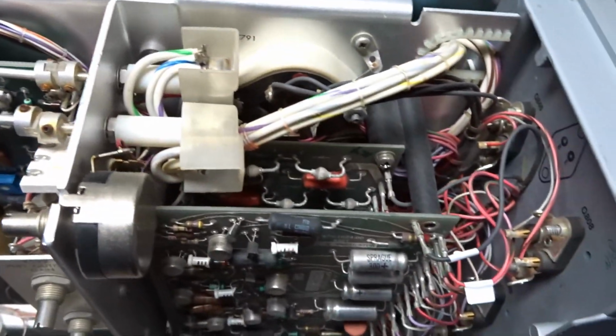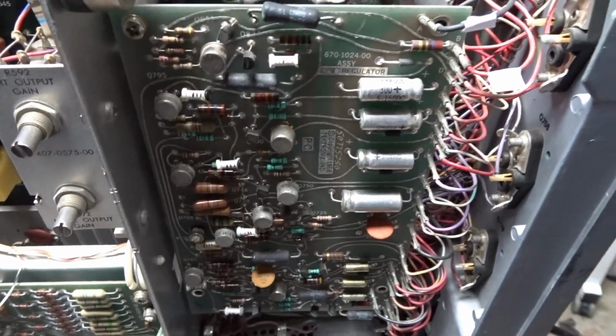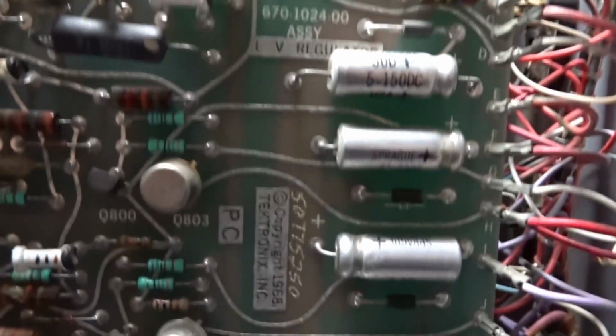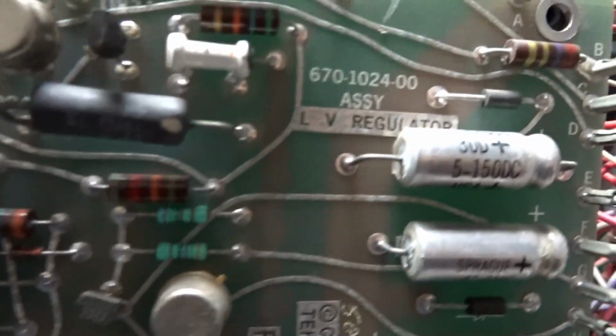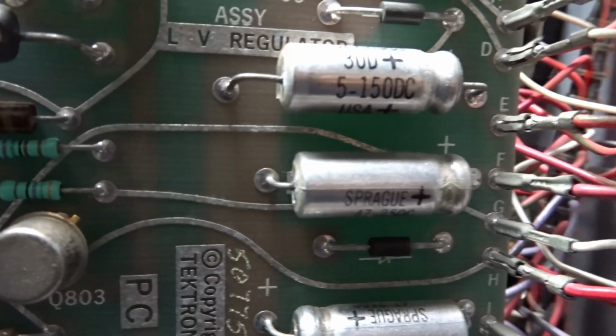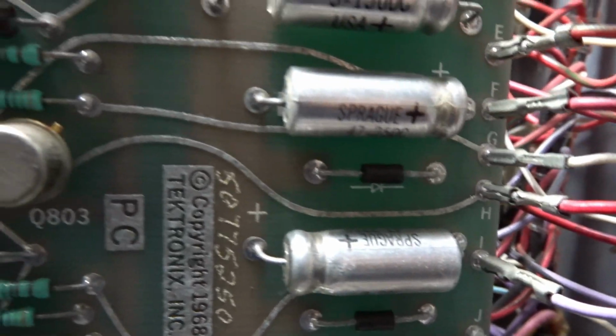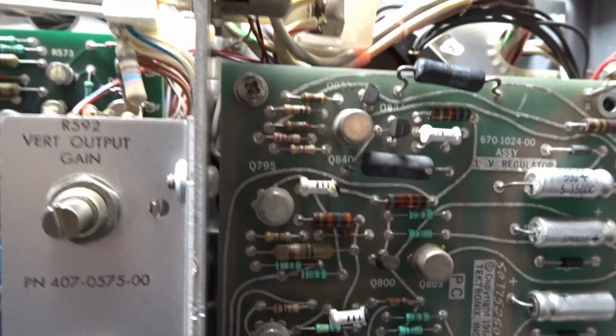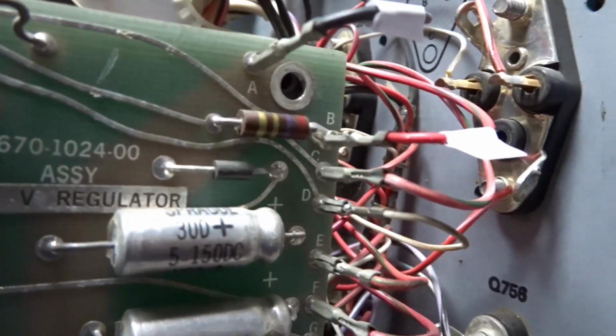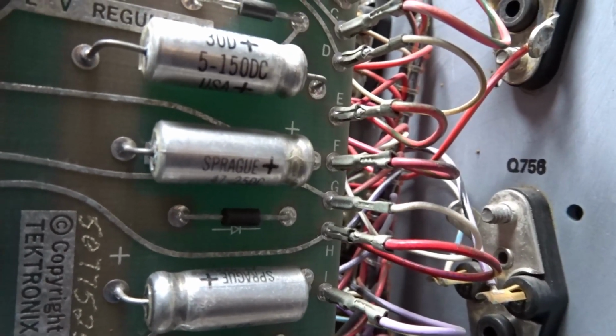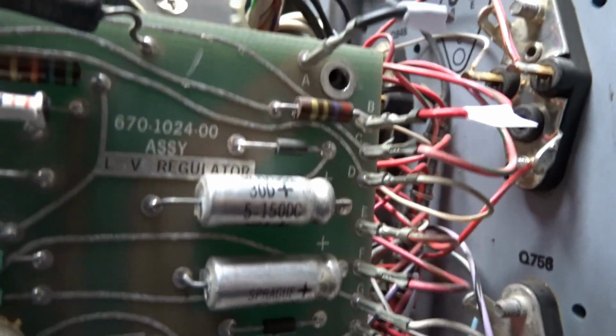Start working on it. My first priority will be checking the voltage around here. This is the low voltage board, and maybe I need to change these capacitors. It's a more than 30-40 year old instrument, and it looks like these capacitors are original, not replaced, so I need to replace them. Working on this device, as you may have seen in other YouTube videos, is not that fast, because as you see, every wire is connected by a jumper. It's not plug and play, and before removing them, I need to label them to make sure I connect them properly once I fix anything on the PCB.